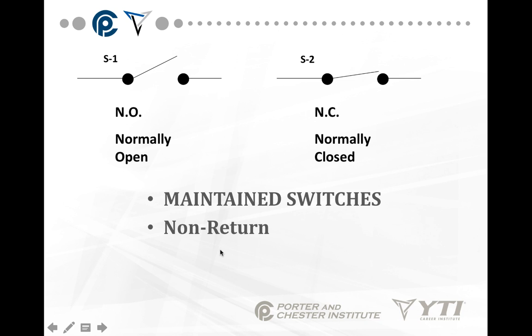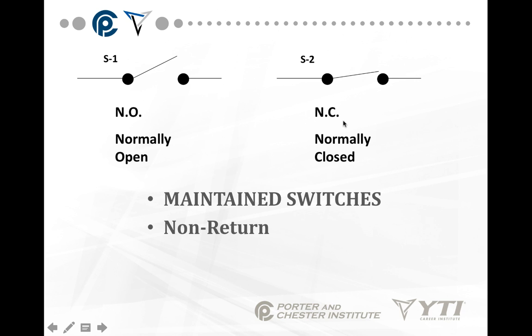We look at the diagrams you'll find on a ladder schematic. Here we have a normally open contact — it is a single pole, single throw. Normally open means it is in the de-energized position, its normal state. To turn the circuit on, you close the switch. If the switch is shown as closed on the schematic, it is considered a normally closed switch. To turn the circuit off — its not-normal position — you would open the switch. So we have a single pole, single throw switch: normally open and normally closed.